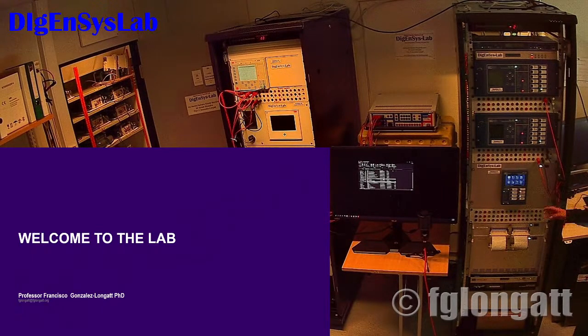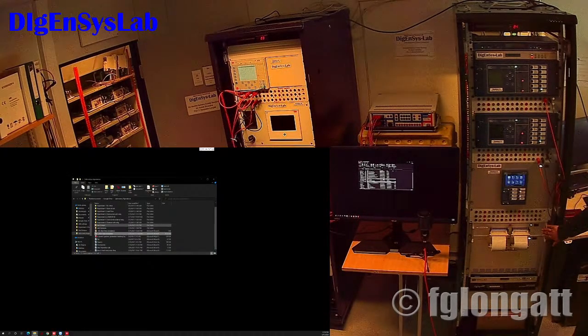I will send some signals from the HIL 604 to the SEL, and it will detect if there is a fault or not, and we will receive feedback to the model to see if it trips or not. It sounds a little easy, but it is not so much because it involves some Python code to communicate with the relay using the word bits.